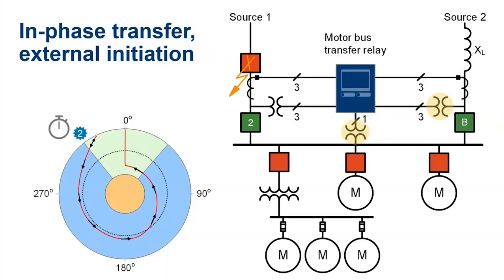And that may happen before. So here in point 4, we determine that if we send the close command at this point and take into account the breaker close time, then the breaker is actually going to close when we are at 0 degrees between the two systems.